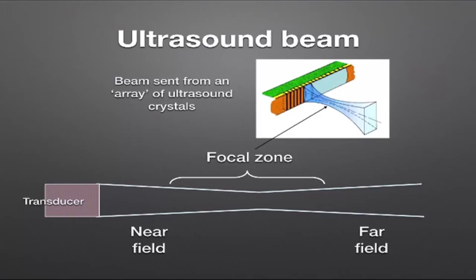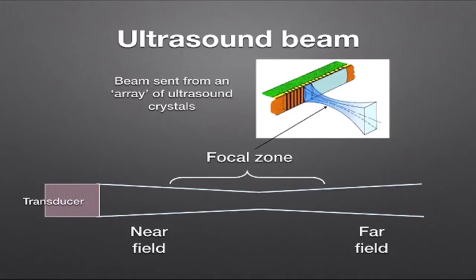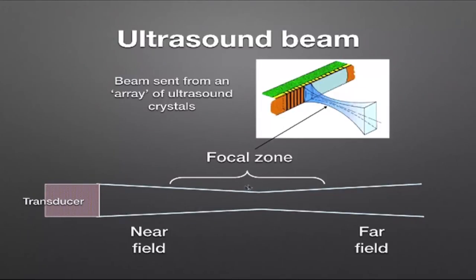The ultrasound beam is made up from a collection of crystals called an array — hence the terms phased array or curvilinear array for different probe types. Drawing a schematic of the beam gives a three-dimensional structure with a near field, a far field, and most importantly a focal zone. In the focal zone, resolution is at its best — this is where the maximum power of the ultrasound beam is.